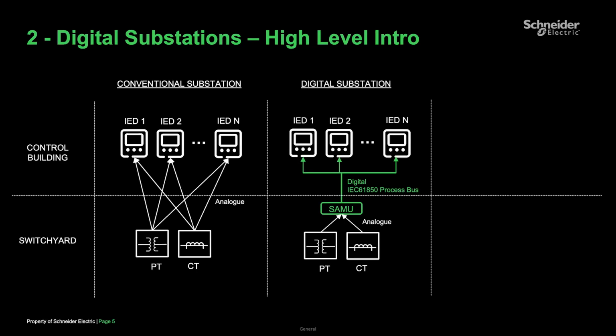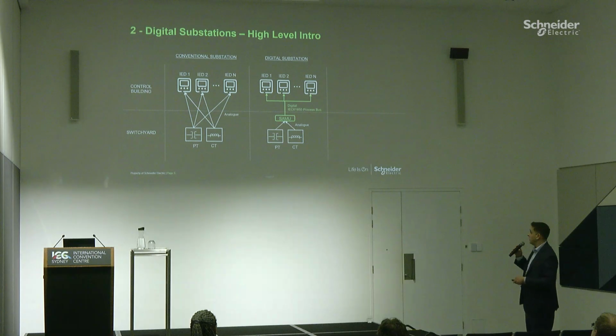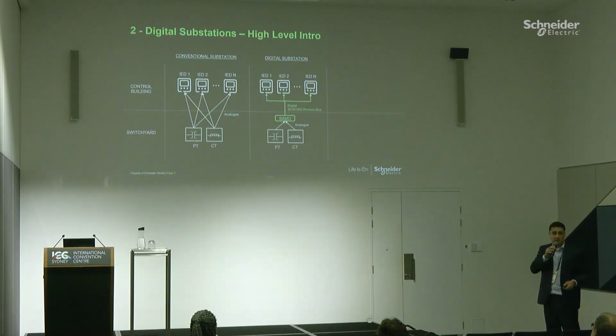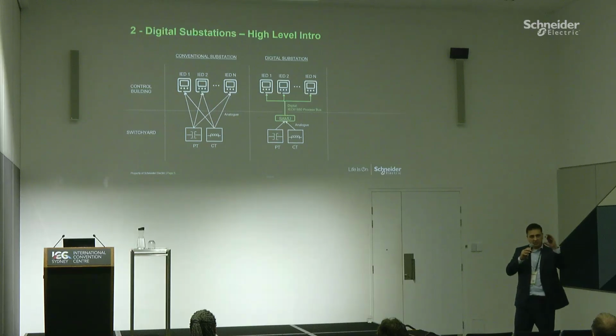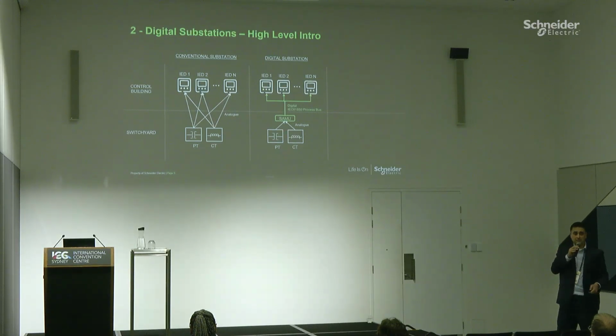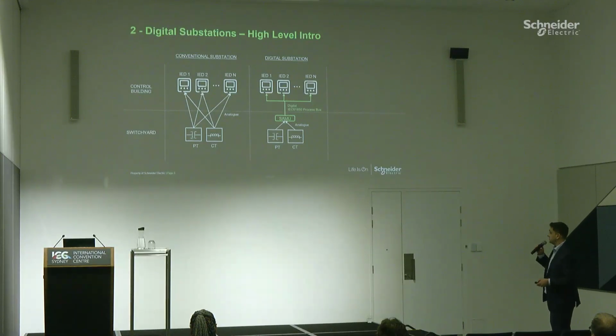Now, the move we're seeing is towards what we call digital substations. This isn't a dream—it's really happening right now. The main difference is this magic box, which we call SAMU, standalone merging unit, or merging units. What they do is convert the sensor signals from analog to digital, and then send those samples using the IEC 61850 process bus protocol—usually done with fiber optics—to the IEDs. So basically, you're uncoupling the analog-to-digital conversion from the device level and centralizing it at this merging unit. We'll talk about the reasons why this is advantageous.